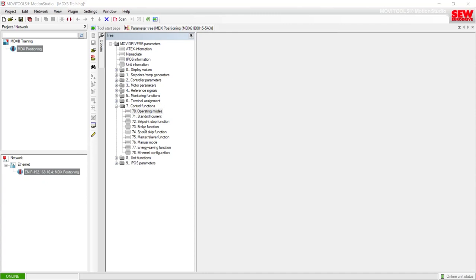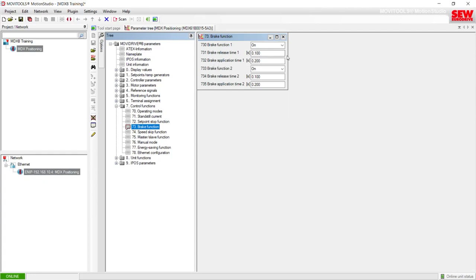Another common item in folder group 7 is the Brake Function, where you can adjust brake application and releasing times. Brake Function 1, Release Time 1, and Application Time 1 are for parameter set 1; Brake Function 2, Release Time 2, and Application Time 2 are for parameter set 2. These brake release and application times are based on the motor startup and what model motor and brake was entered. In normal situations you wouldn't need to adjust these — I recommend leaving them to what the motor startup proposes. Manually changing these to an incorrect value could introduce a safety issue such as a load falling with hoists or premature wear to the brake disc, affecting stopping and holding torque.